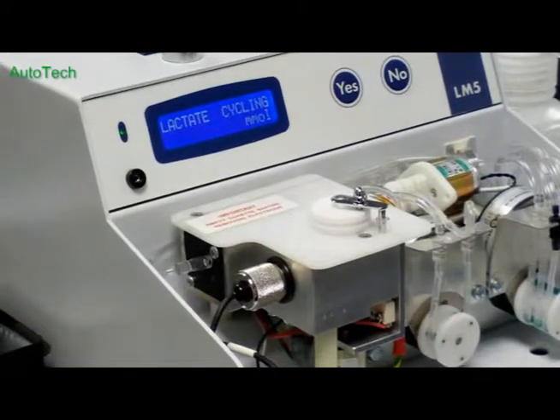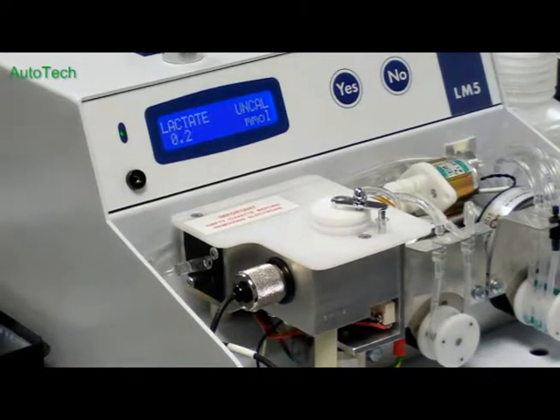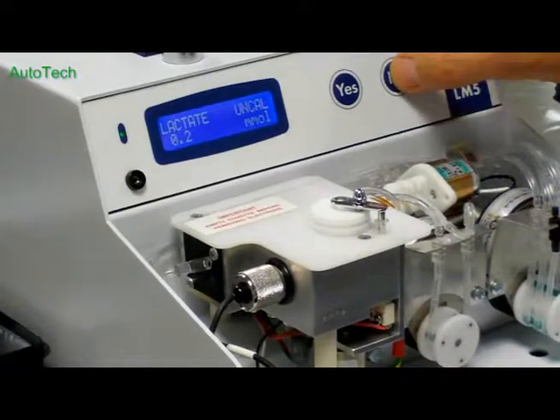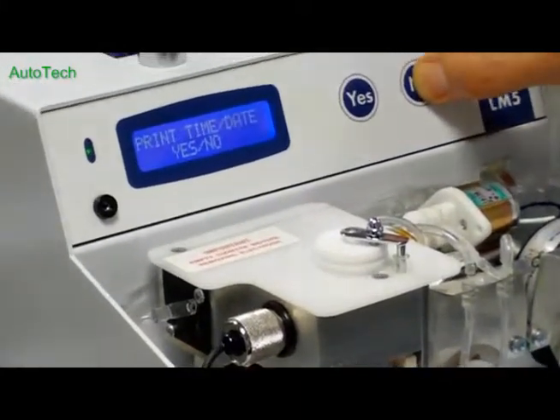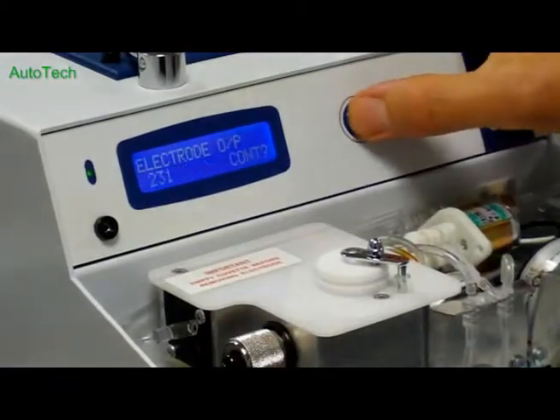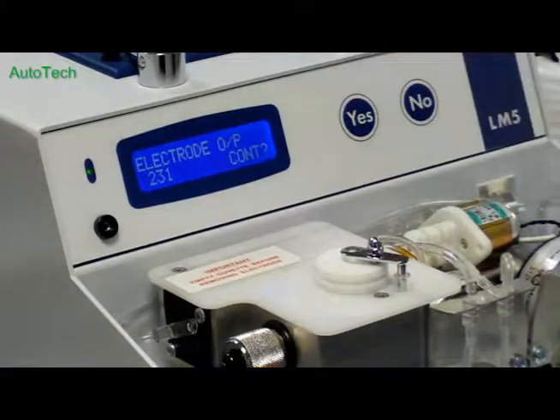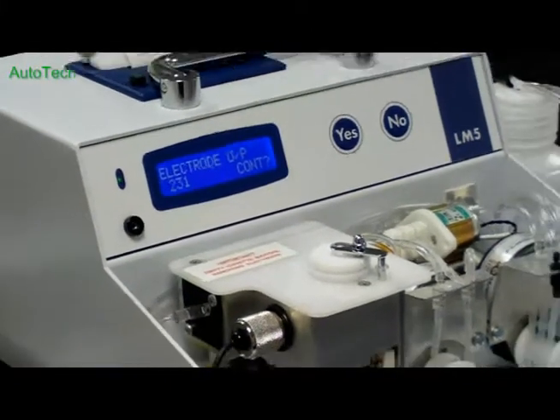It will take roughly 20 minutes for the electrode to stabilize after being made up. So if we have a quick look at the electrode output by going through the menu, electrode output, and already it is stabilized and that is a normal reading.